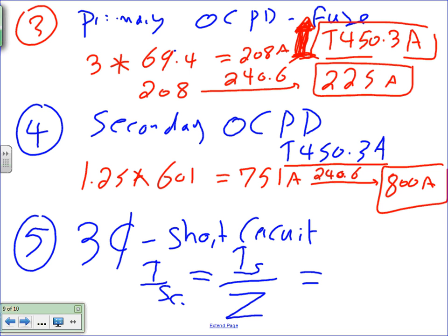Well, our secondary side isn't over, it's less than 600 volts. So then we'll go down here. No, you go to the same table for the secondary side. Oh, we still use the same table. Same table on the secondary side, even though we're under. You use table B if the primary and, not or, the secondary are both 600 volts or less. That's when you use B. For all other cases, you have to use A. MV cable on the primary. On the secondary, it's like any other cable. Okay, I can finish this one in a second. Let me just do a short circuit.